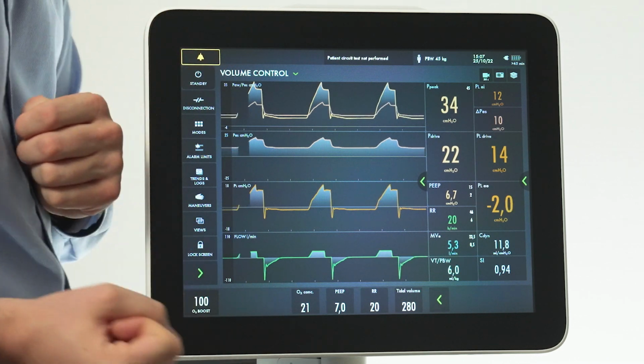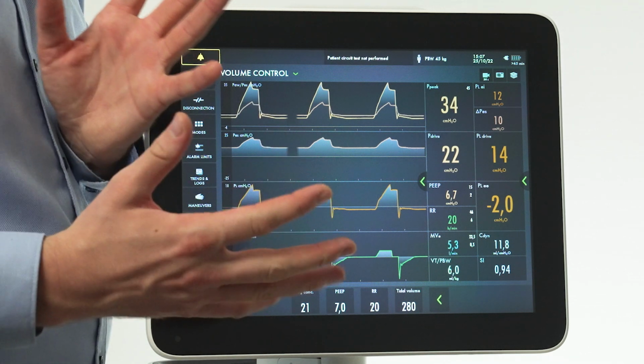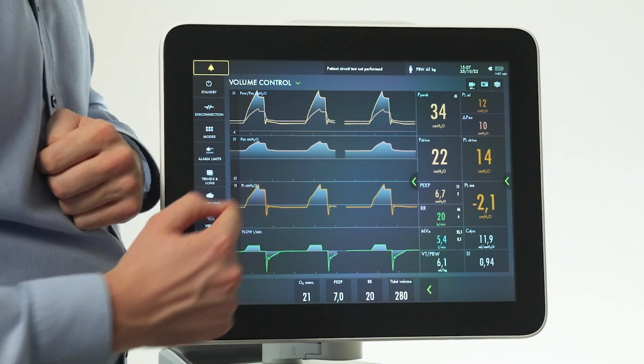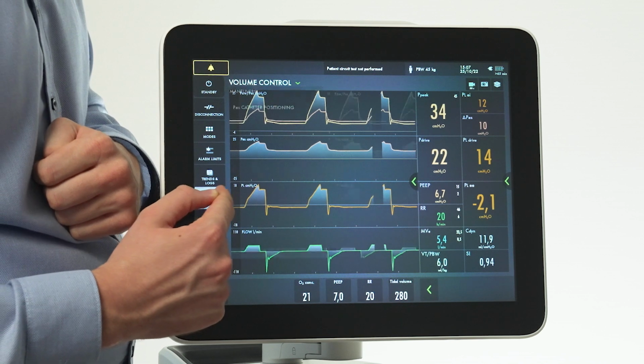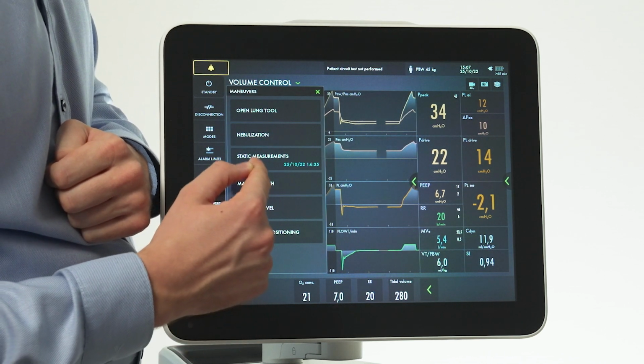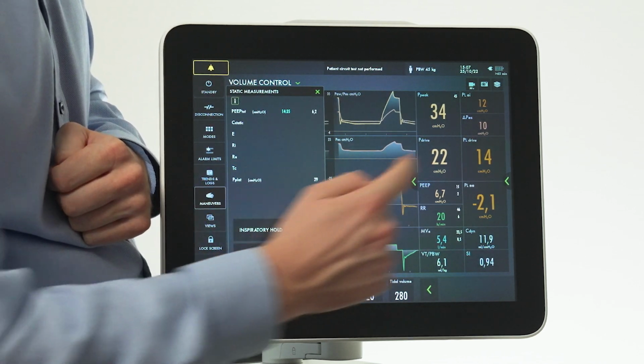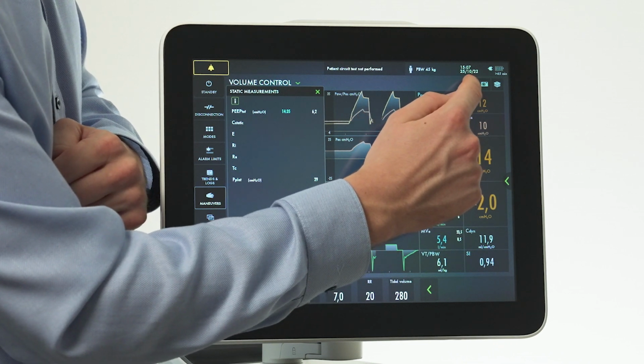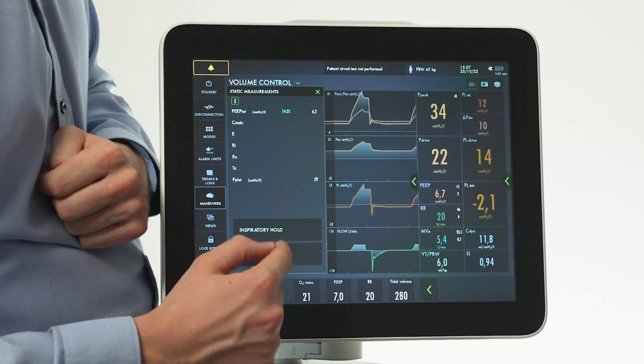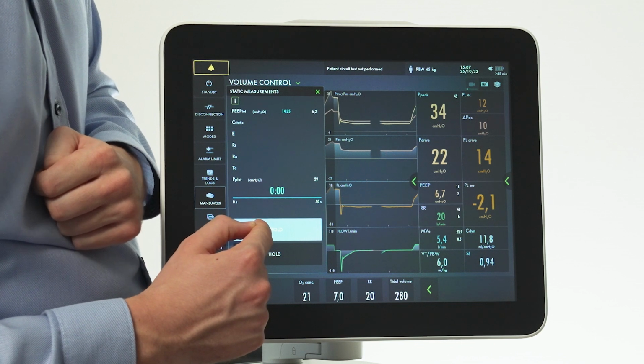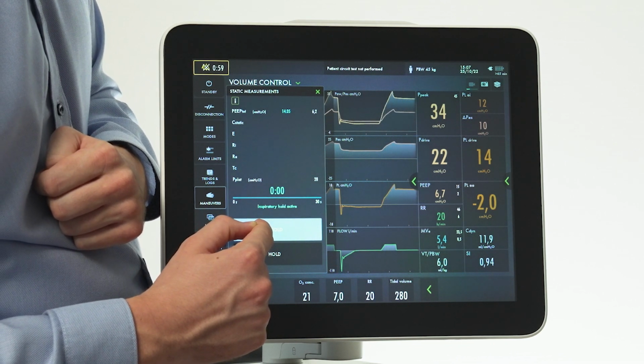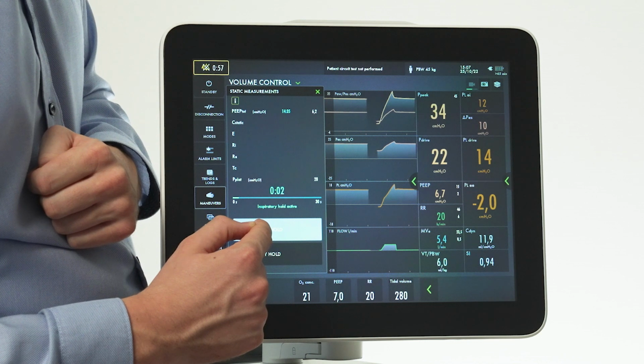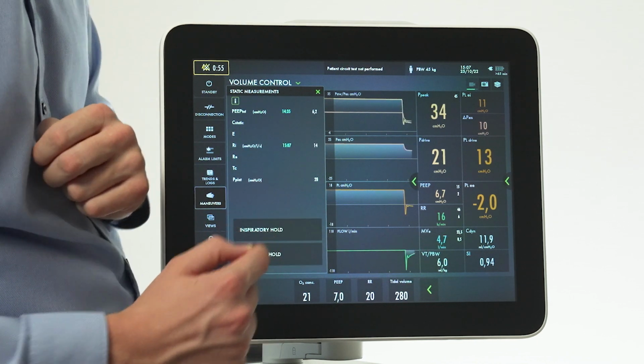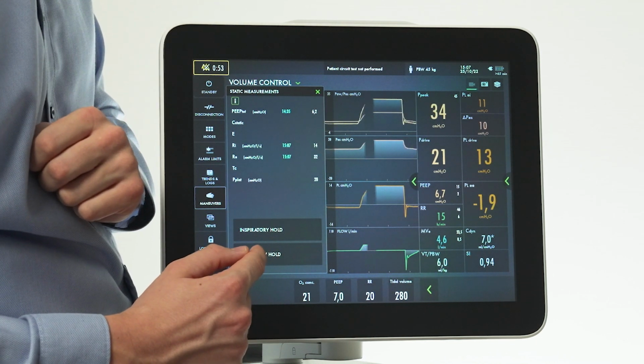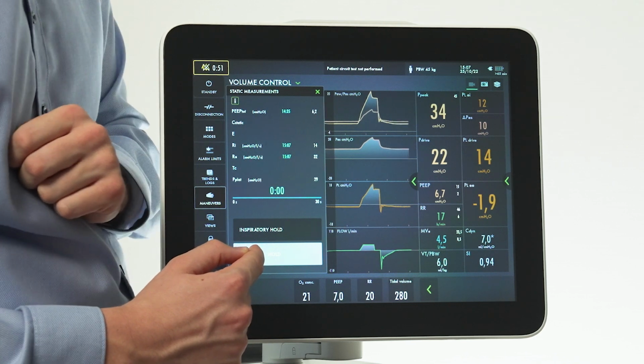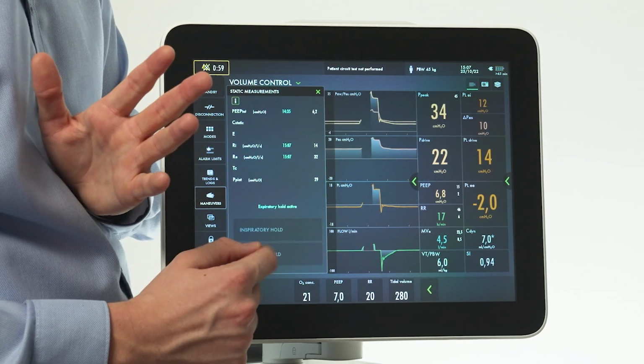What I'll show you right now is how you can obtain those static measurements. What I'd like to do is go to Maneuvers, Static Measurements, press the recording button at the top right corner of the screen, and start with an inspiratory hold. And I'll hold this for about 3 to 4 seconds. This is usually enough to get a reliable plateau, release it, and then in the next breath I'll give an end expiratory occlusion for 3 to 5 seconds.